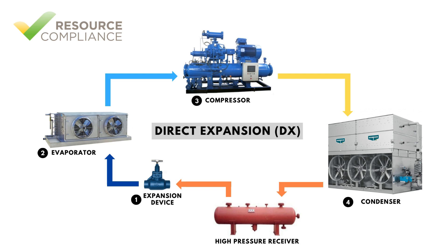The compressor process reduces the volume occupied by the refrigerant, which results in higher pressure as the refrigerant exits the compression. Additionally, when refrigerant vapor is compressed, the temperature of the vapor increases. This is called the heat of compression and is added to the heat already absorbed in the evaporator.